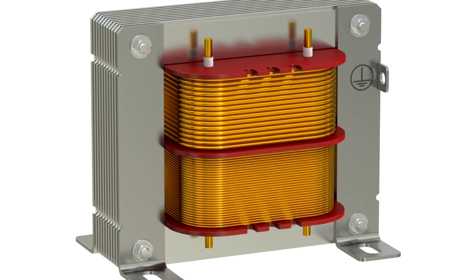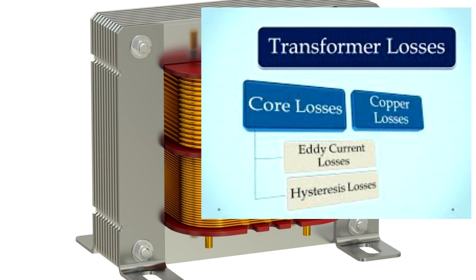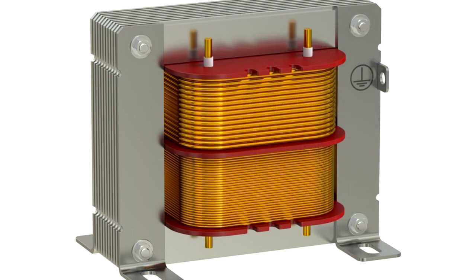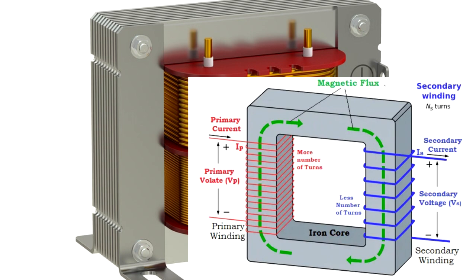The second group of losses that can occur in a transformer are called core losses, although they are very commonly referred to as iron losses. Iron losses and core losses are the same thing. Sometimes I think it's easier to think of a transformer like a machine, and like a machine it has different components. You have a primary winding, and the purpose of the primary winding is to induce a magnetic field. It creates a flux in the core of the transformer. That magnetic flux travels around the core until it meets the coil of wire which forms the secondary, and that magnetic flux is converted back from magnetic energy into electrical energy.